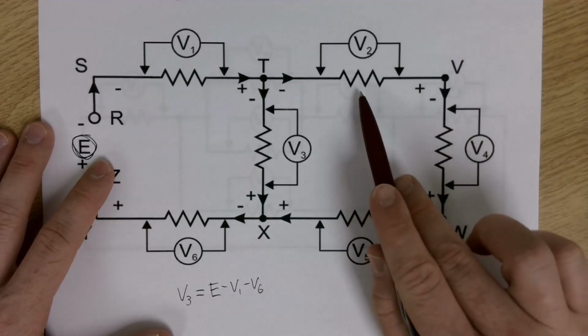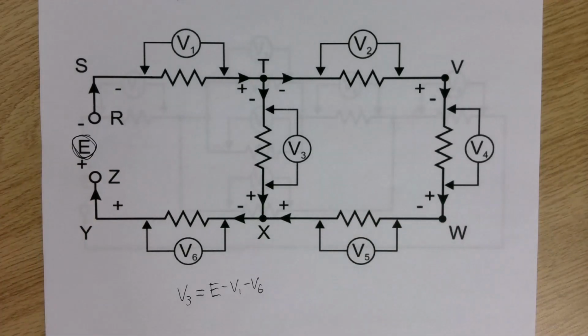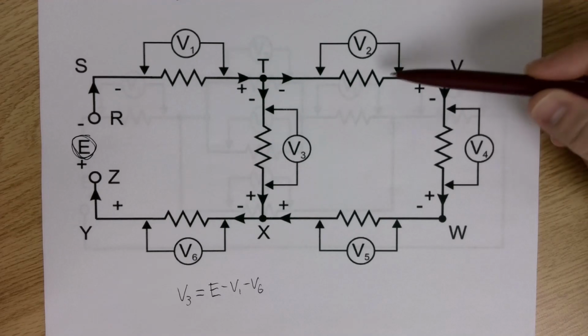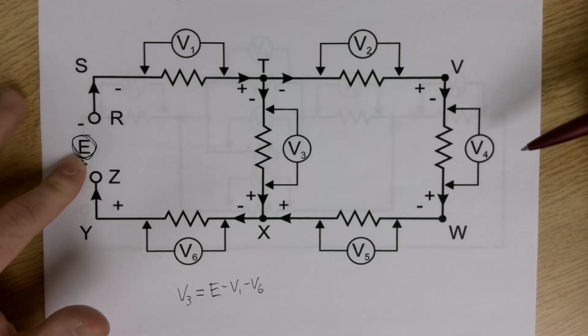This type of volt drop does happen because of the distance that we run our wires sometimes. So if you run a wire too far, you're going to have too large of a volt drop on the wire, and then the load that you're trying to power might not have enough voltage because it's too far away from your source.